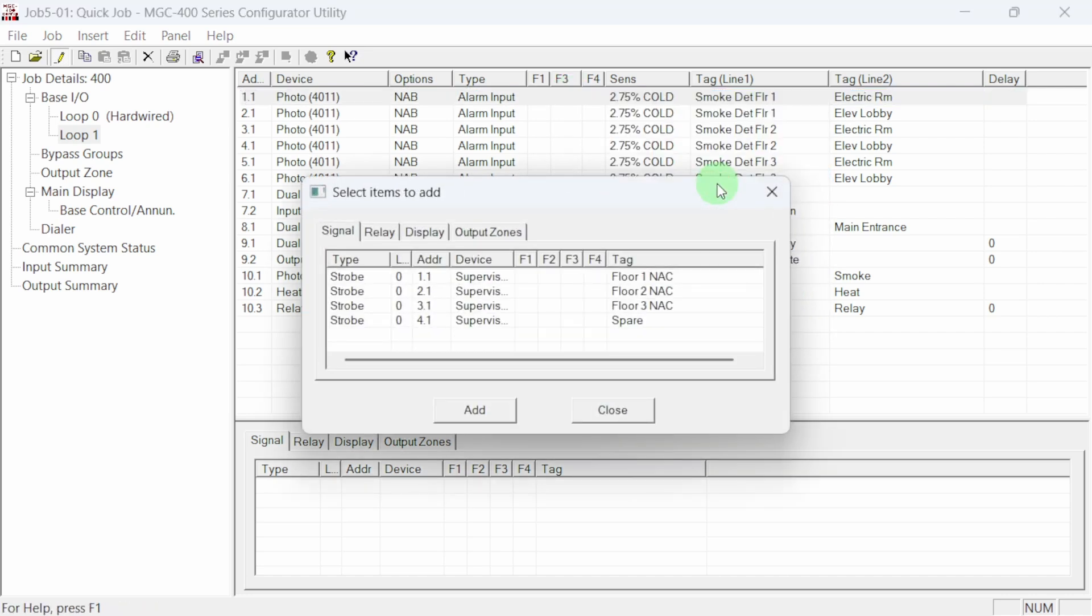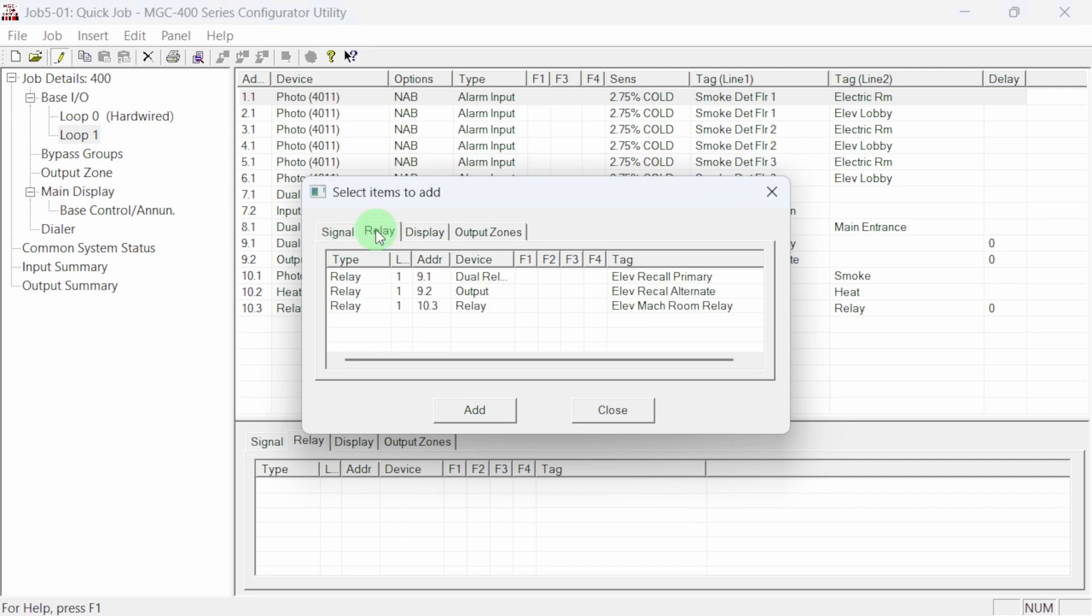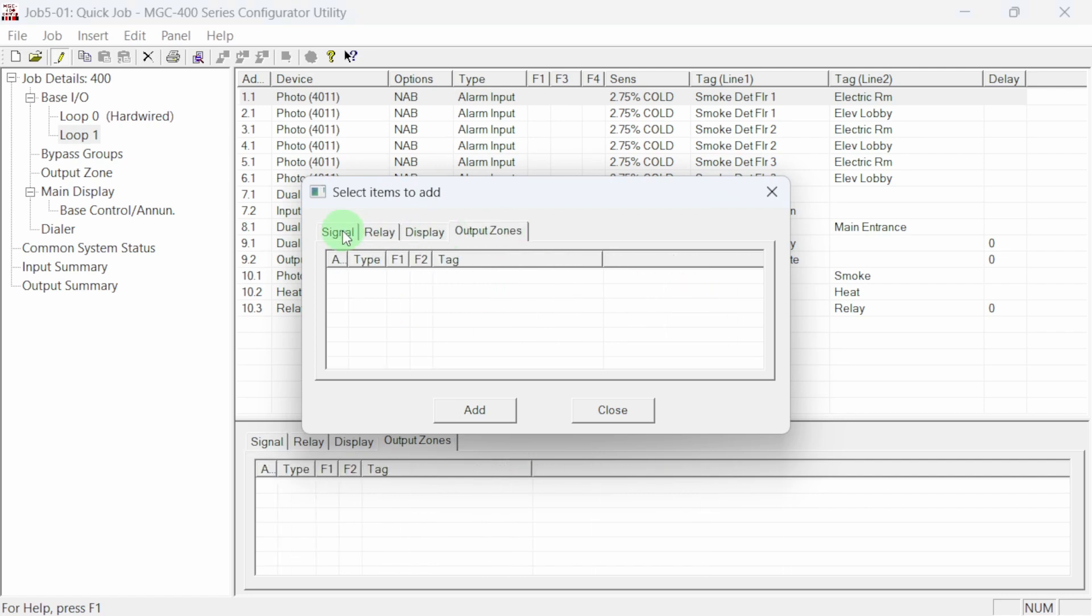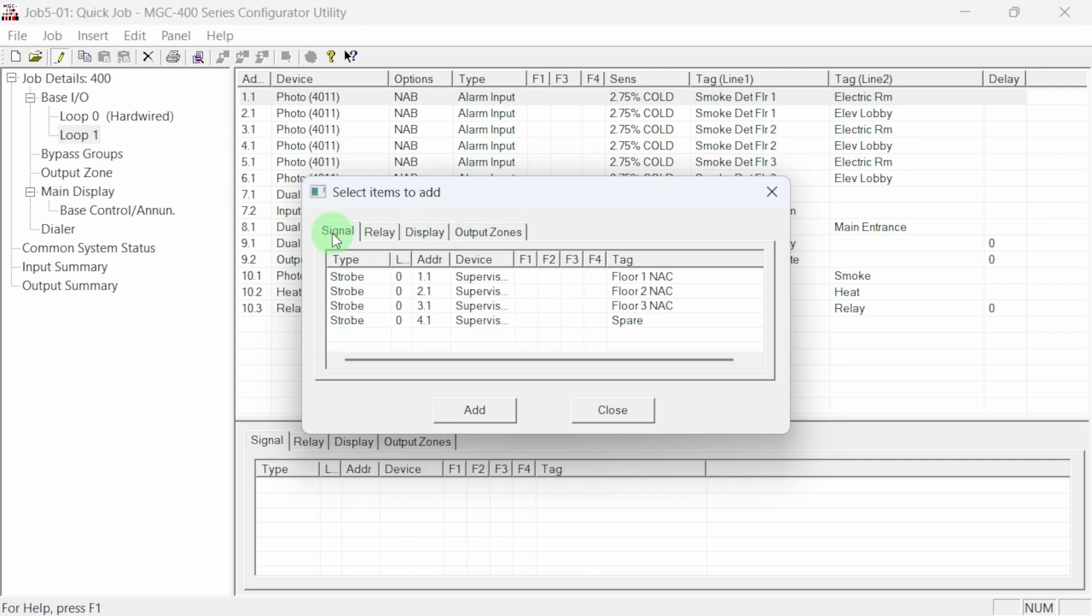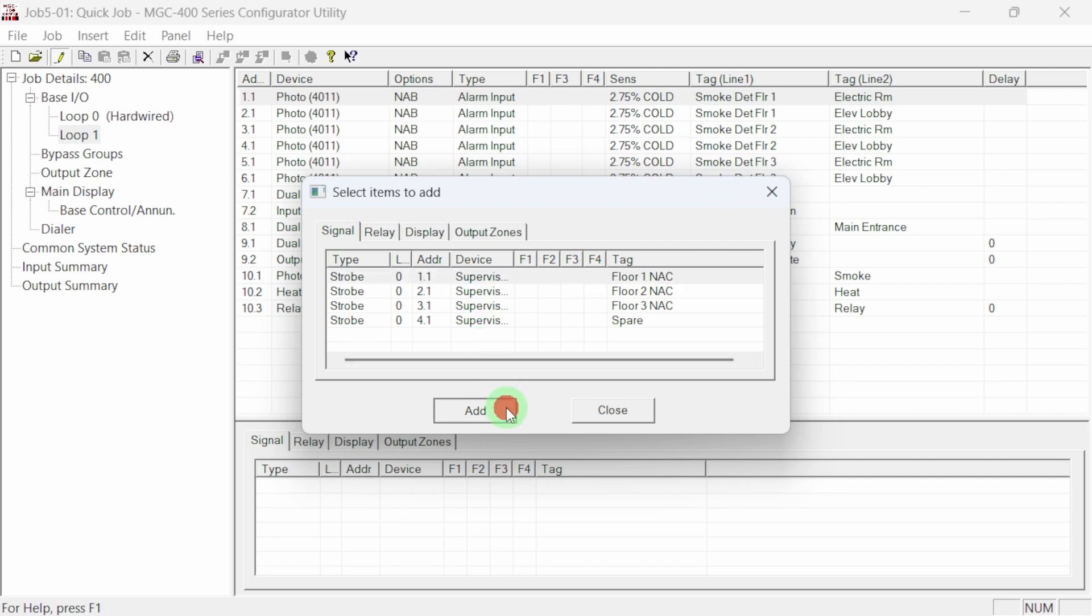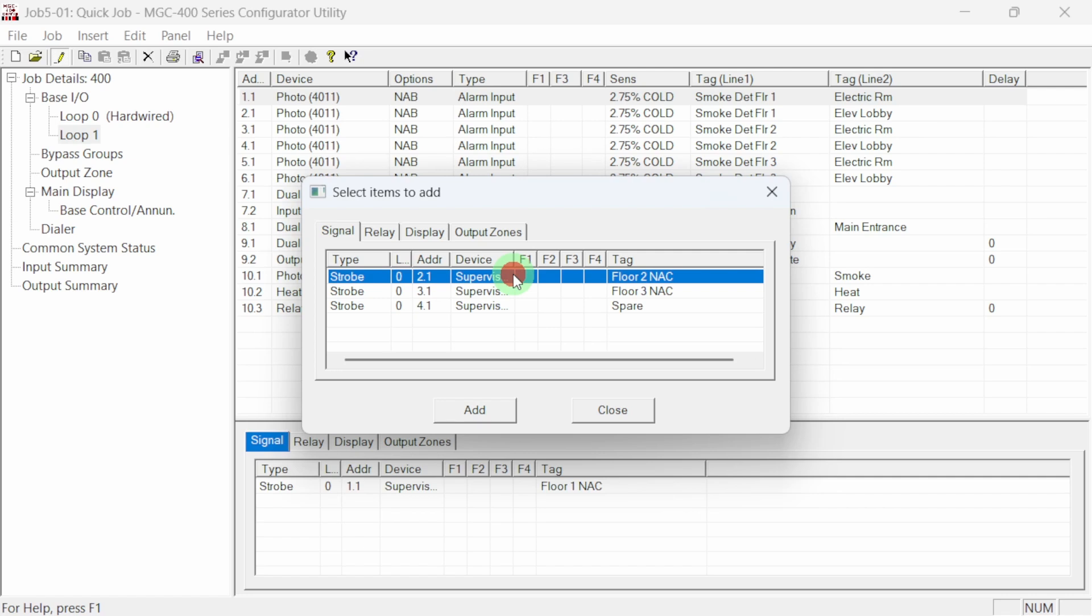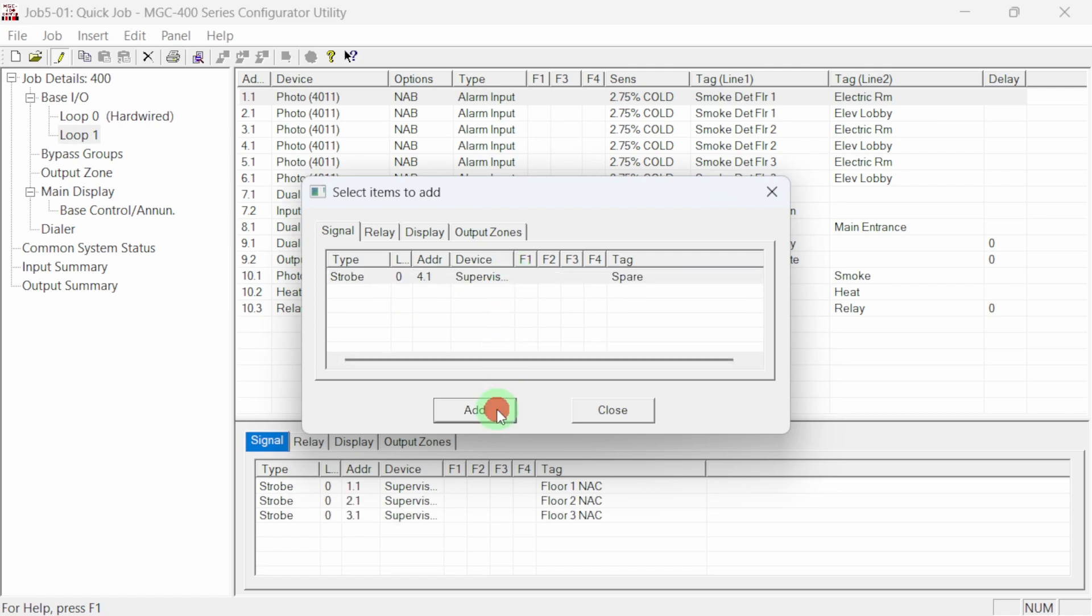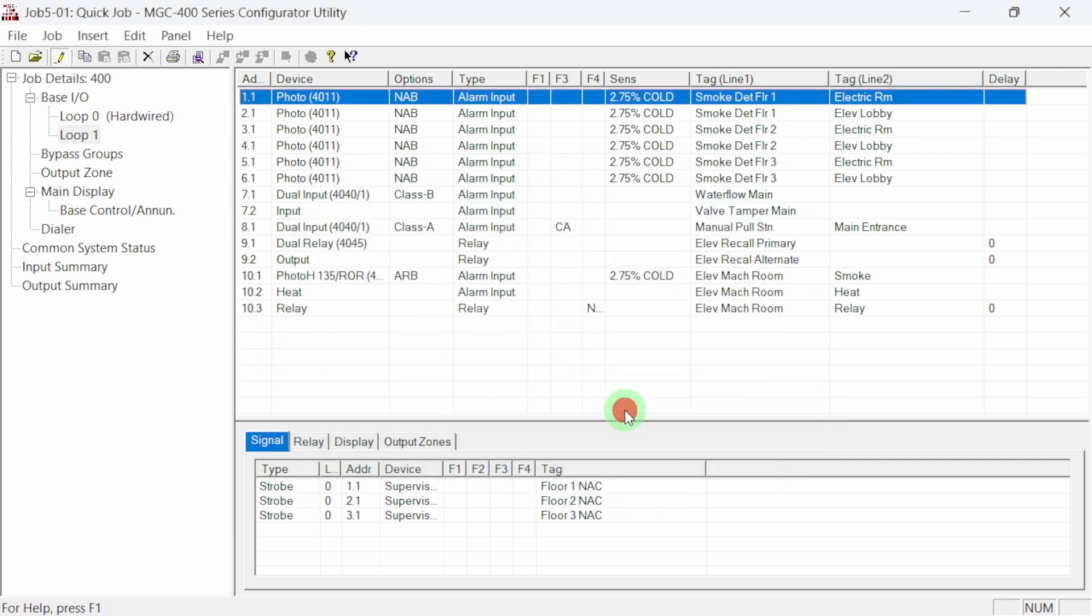A dialog box opens where we can choose and add circuits that will trigger when the device we selected is activated. We can trigger signal circuits, relay circuits, display LEDs and output zones. Let's add three of the NAC circuits to our selected smoke detector. Highlight the circuit and click on add. The circuit is removed from the selection box and is added as a correlation to the selected device. You can also double click an item to add it directly. Close the dialog box and review your correlations.